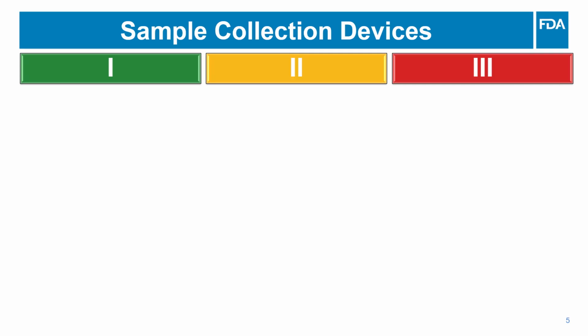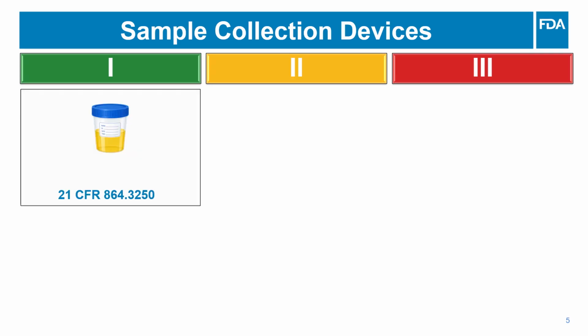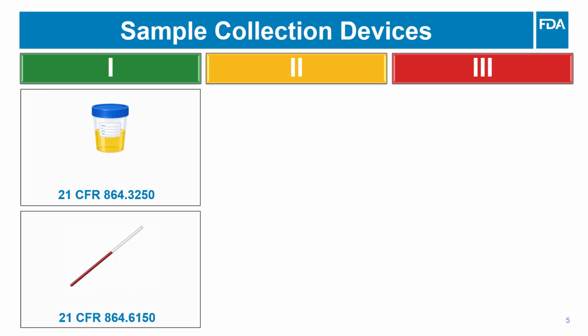Here are some examples of different types of sample collection devices and their current classification. Many basic receptacles, like simple urine cups, are Class 1 and often exempt from submitting a 510K. Another example are the straw-like capillary tubes that are part of the manual hematology devices under 864 Subpart G of the Code of Federal Regulations.